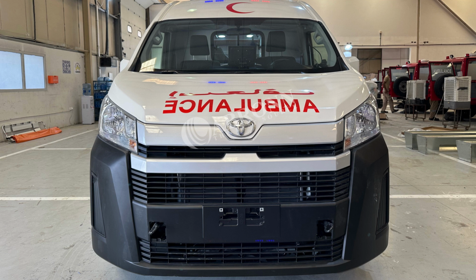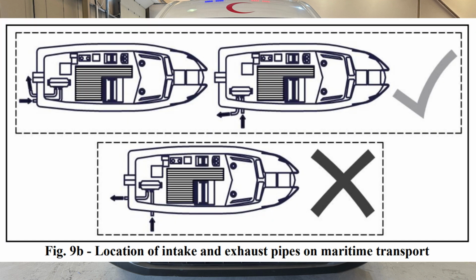Disregarding this recommendation can lead to the opposite movement of the flame towards the air pump fan, resulting in the melting of the air pump fan, and to the burning of the heater. The air intake must not be installed in the movement direction of the vehicle or vessel. In cases when the intake of clean air cannot be ensured, such as off-road and special-purpose vehicles, please mount the dedicated Autoterm air filter.